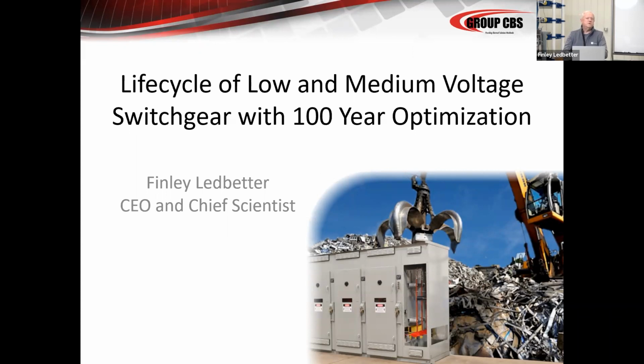Moisture is a big deal. Airborne contamination is a big deal. Spider webs, dirt, carbon black, titanium pigment, iron ore, whatever's in the air is a big deal. But with a vacuum breaker, at least the interrupting part of it is sealed in a canister, in a container, so it's somewhat isolated, and it takes very little energy. So vacuum pushed aside the air breakers. A lot of that was economic because the hours that it took to maintain the old air breakers obviously cost the plants a lot of money.